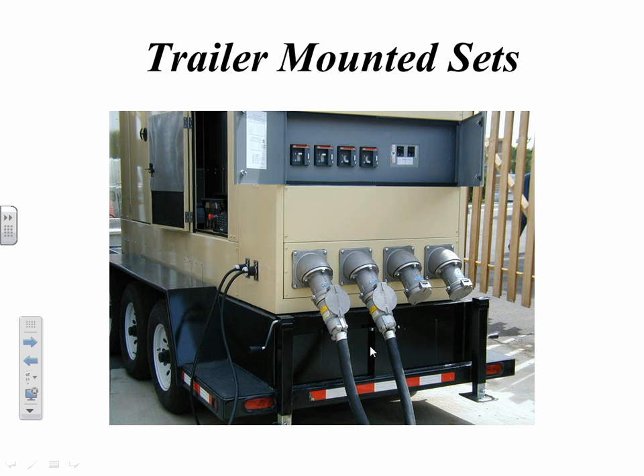But the other thing we can do is we can make different voltages, because these lift stations might be 120, 208, three-phase over here. This one might be 277, 480. Maybe we want to be able to take it to the well, so that'll probably be at 480 with a reduced voltage transformer on it, right by the water tower. Or maybe we even have something in the garage and that's single phase. So we put a switch on a trailer mounted set that allows us to change voltages just by flipping the switch. We drag it to when there's an outage and the lift stations need to be pumped down. You just set it on the voltage we're going to first, pump that lift station down, then drag it to the next one, turn the voltage over to 480 or whatever we need, and keep going. It's a very handy thing for a utility to have.